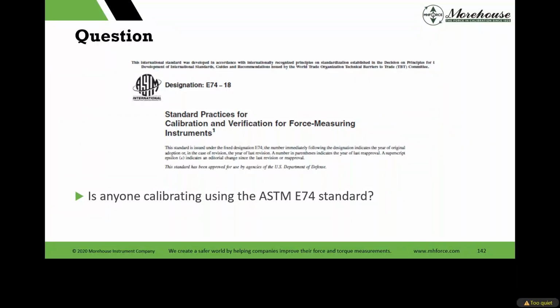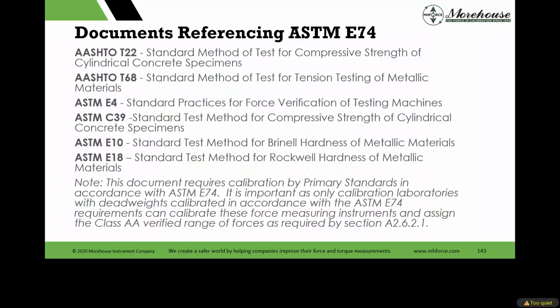So we had that. About 31% are calibrating to E74. The new standard should be out this year, and it should be E74-25. Not much is changing. Some subtle changes, and I'm not too big on most of them. Changing things to elastic force instruments, some word changes specifically in the standard. There's a dumb line in the standard that says for simulators you shall follow the guidance in the annex, and the annex is non-mandatory, so that's going to be corrected to a should. Not too much meat or worthwhile changes are coming. Nothing really to the calculations or anything else.